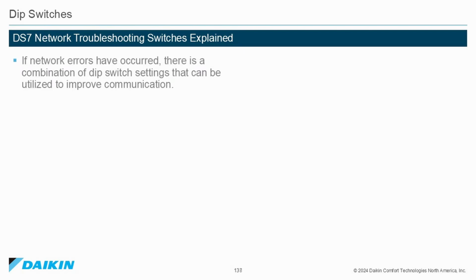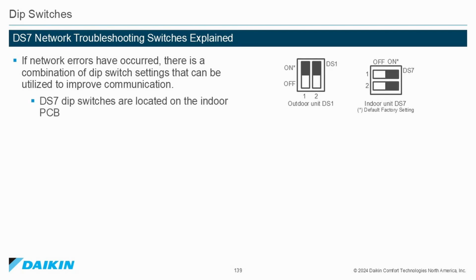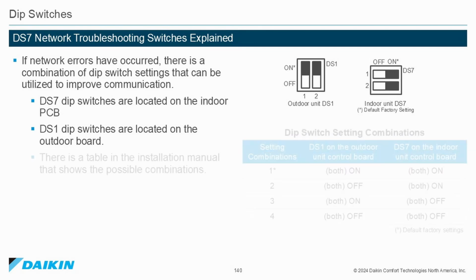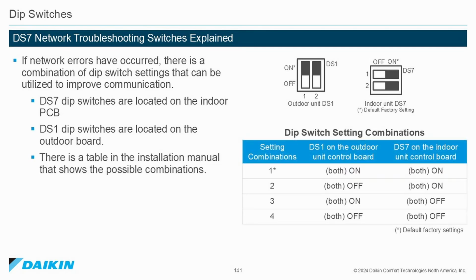Dip switch 7 network troubleshooting switches explained. If network errors have occurred, there is a combination of dip switch settings that can be used to improve communication. DS7 dip switches are located on the indoor unit printed circuit board. DS1 dip switch settings are located on the outdoor unit circuit board. There is a table in the installation manual that shows the possible combinations.